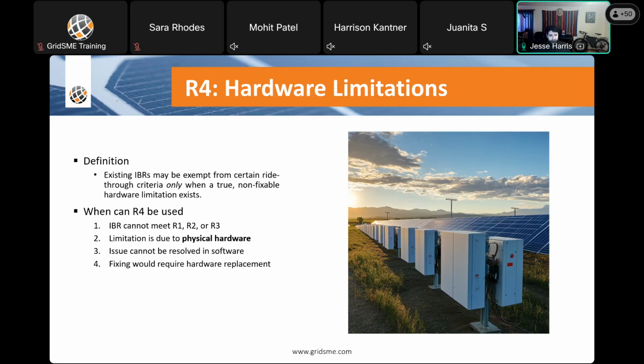So definition is existing IBRs may be exempt from certain ride-through criteria only when a true non-fixable hardware limitation exists. So when can this be used? Well, any of those 3 requirements that I just listed above, R1, R2, R3, your IBR cannot meet them, and the limitation is due to physical hardware. That is to say, it can't be fixed in software, and to actually solve the issue would require a hardware replacement.